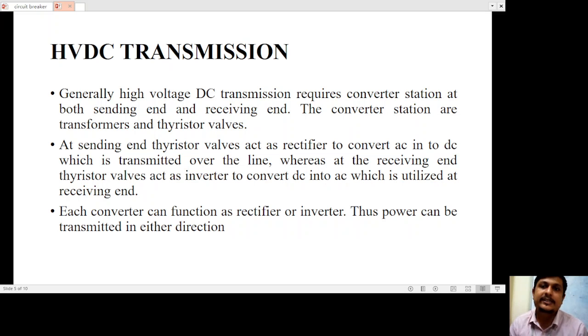Generally, HVDC transmission requires converter stations at both sending and receiving ends. The converter stations consist of transformers and thyristor valves. We generate power in AC form, but we convert it into DC and transmit it, and it is also converted back into AC at the receiving end station, from where it is distributed to the consumer.